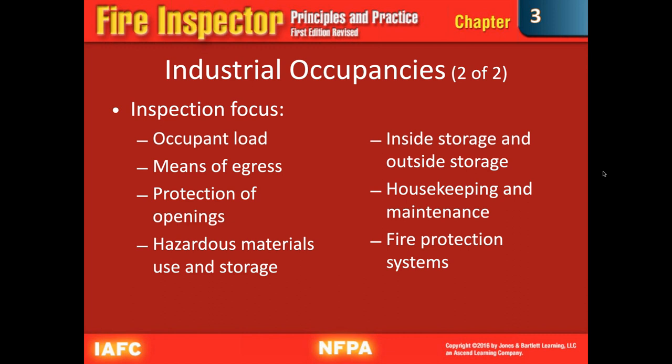And when you get down into your fire protection systems, you're going to be looking at things like the fire alarm detection systems, portable fire extinguishers, water supplies, fire pumps. If they're excessively large places and their sprinkler systems go either a very long distance, or if they have standpipes of some sort that are already charged, they may have fire pumps built in. Standpipe systems themselves, sprinkler systems, and special extinguishing systems.